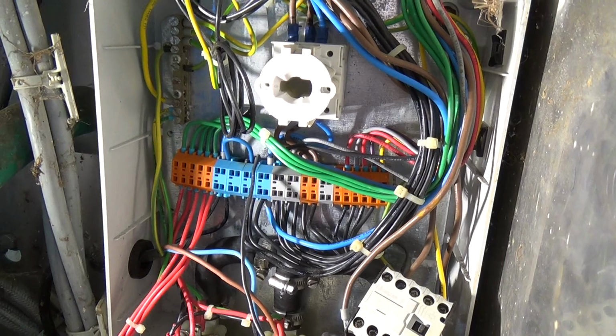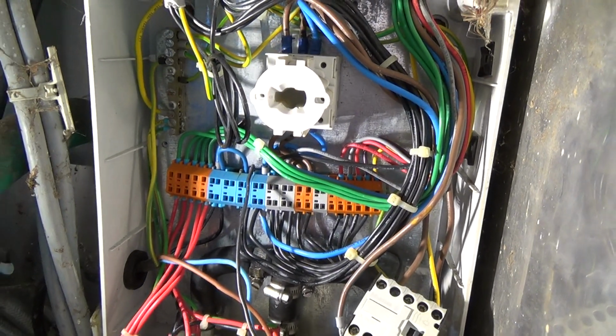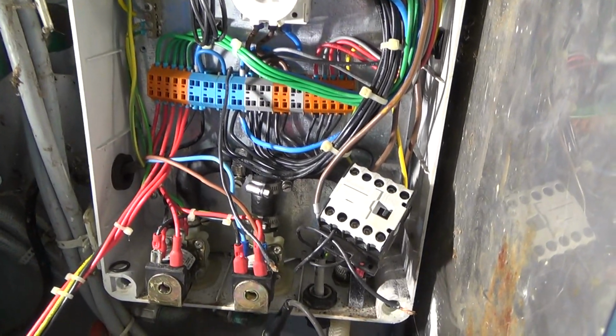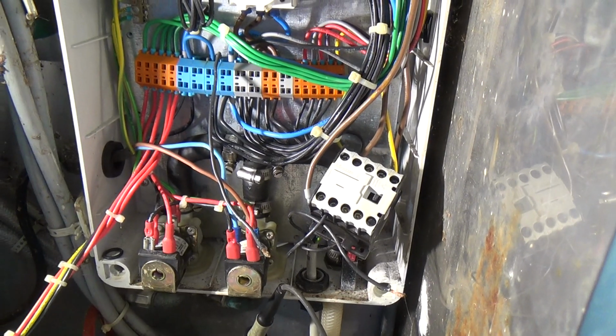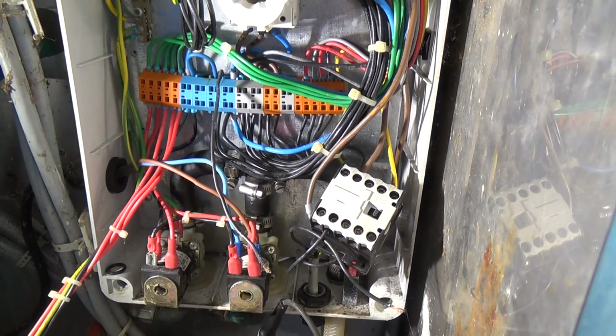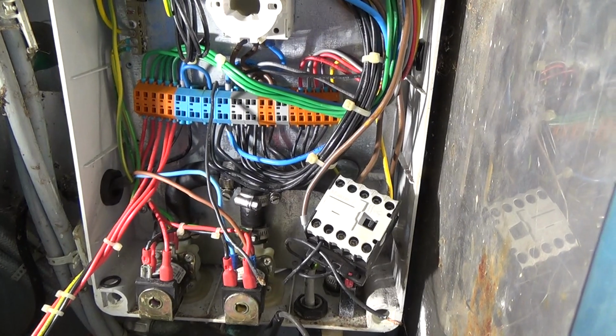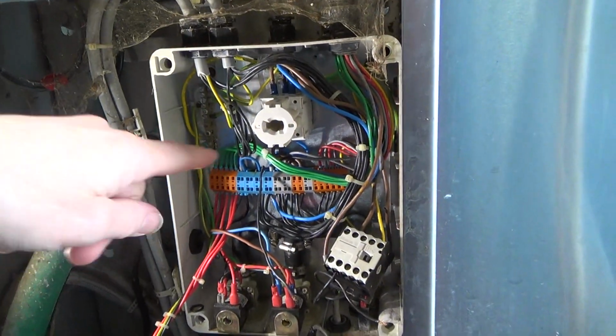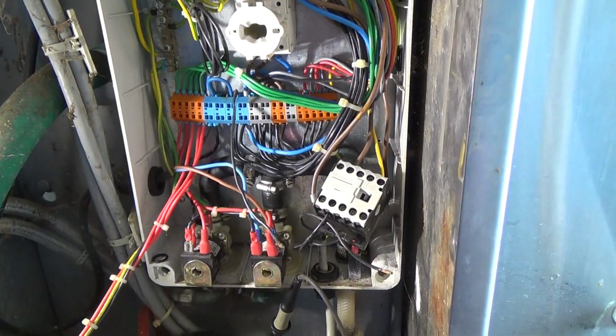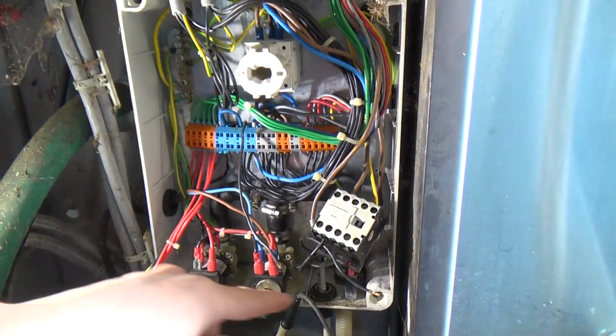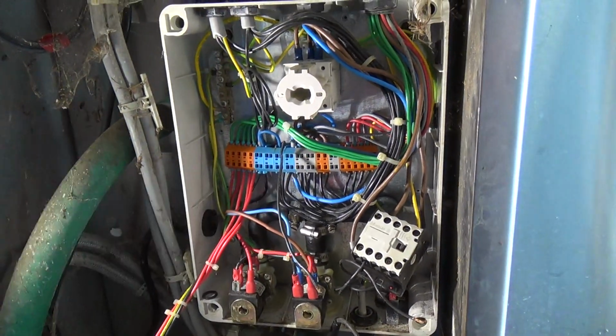So we might be chasing a fault that doesn't actually exist, because we might be just chasing the main neutral connection for the supply, which is really important. Why you need to isolate your neutrals when you're Megger testing. Let's get these two put back in here, and then we'll have a closer look at what's going on.